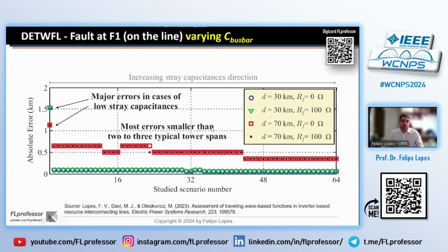These effects from the point of view of fault location, we can see that when these capacitances increase, very accurate response can be found, but when these capacitances decrease, we start to see additional errors, and it shows that fault location can present higher errors for cases in which stray capacitances are small in the system.